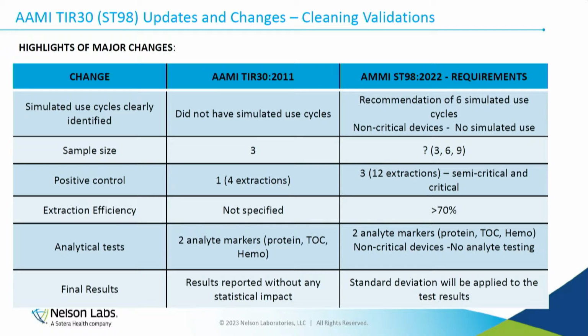Some of the major changes from TIR30 to ST98: there were no simulated use cycles, and they have implemented the simulated use cycles now. The controls have been identified, there are more controls you have to do, and interpretation of data and what kind of analytical markers you have to test are specified. In this chart, you will see that non-critical devices, these are devices that contact intact skin or are sitting in the operating room on the sides, that are non-patient contacting, we don't have to do analytical tests anymore. We just have to do visual inspection and you're fine. That's in the ISO and that's in the AAMI. So one thing we aligned with the ISO was the non-critical portion of the devices. That is the first forward step that we have made towards that.